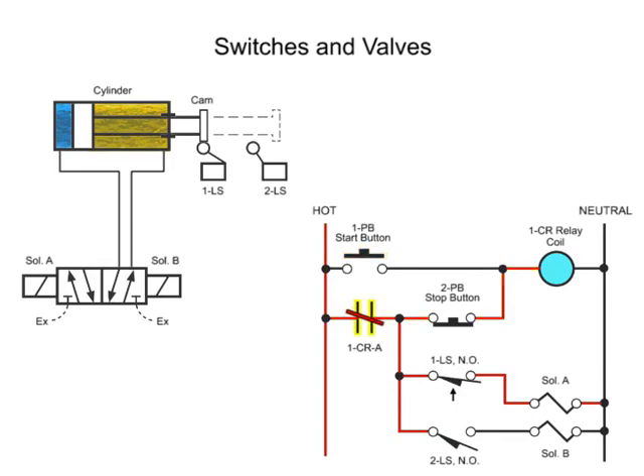When contacts 1CRA are closed, electrical power is distributed to the rest of the circuit. Since limit switch 1LS is held closed by the cam prior to the beginning of the cycle, current flows through this switch and activates solenoid A. Since limit switch 2LS is open prior to the beginning of the cycle, current cannot flow and thus solenoid B remains de-energized.